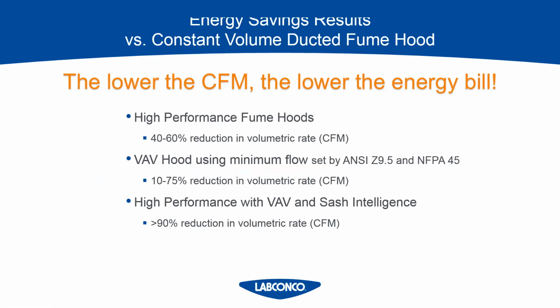So that brings us to the best case scenario, using a high performance hood that is on a VAV system and has sash intelligence. What that means is the hood has a motion sensor to detect a person's presence. And if the sensor doesn't detect motion, then the sash will shut. And that's when you'll reap the benefits of the lower CFM. So these can save at least 90% of the required air consumption compared to a standard fume hood at a constant volume. So it's quite significant there in the change.